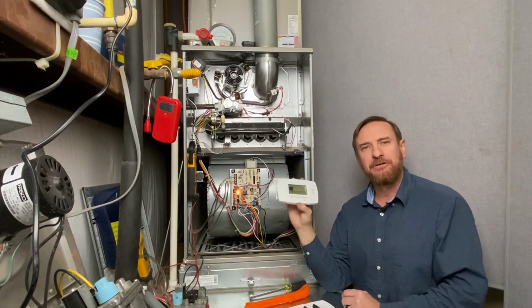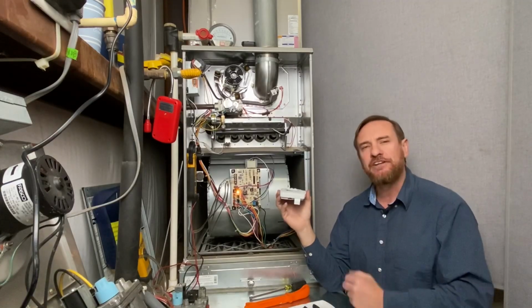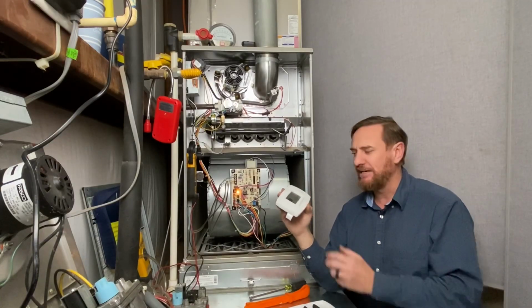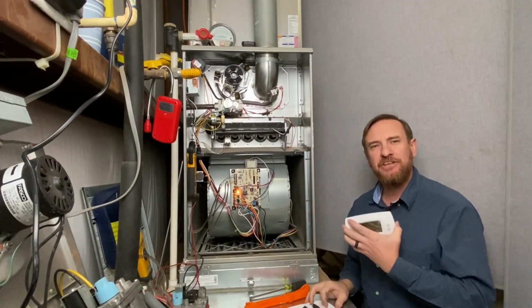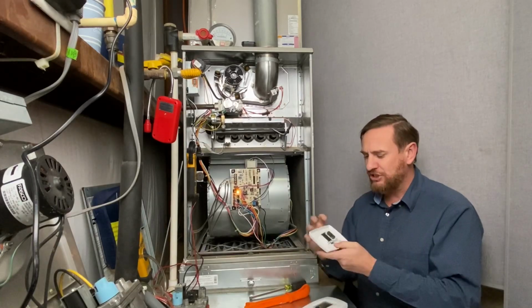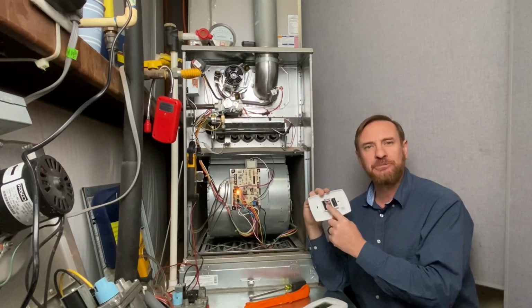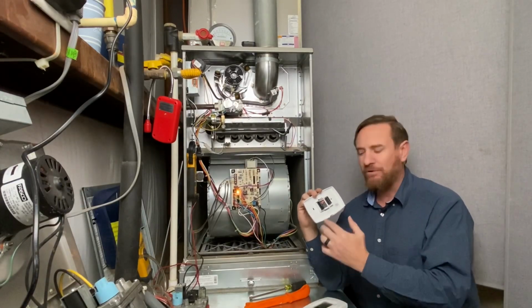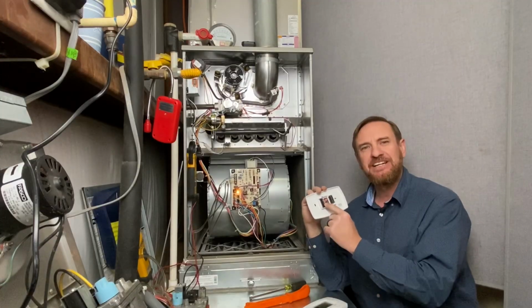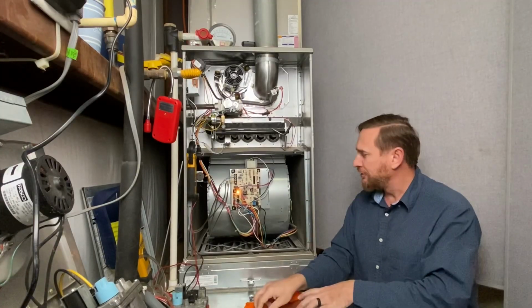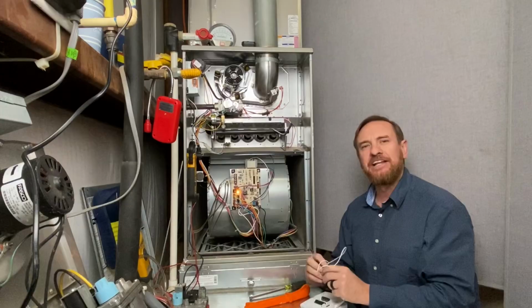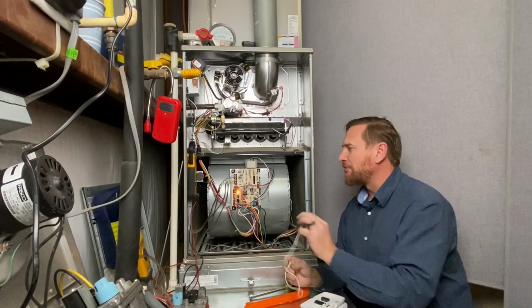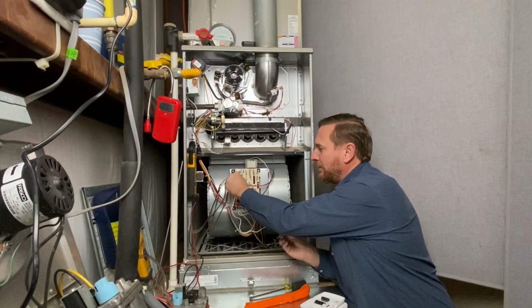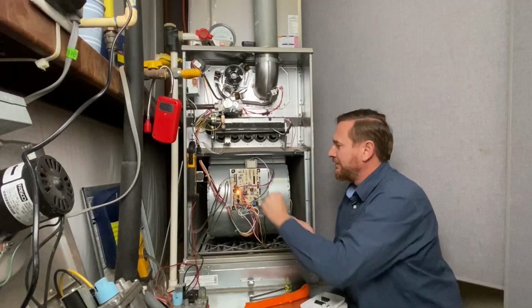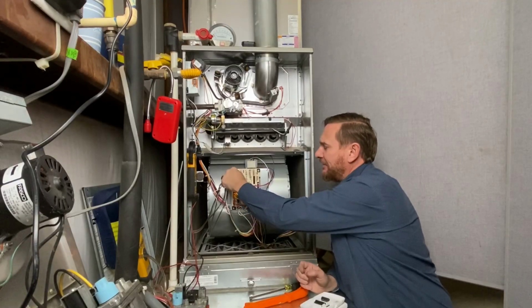One step is the thermostat calling for heat. The phrase calling for heat is a vocabulary term that we use in the trade. The thermostat's nothing more than a switch. That switch connects the R and the W terminal. You can use any color wire you want, but the terminals it's connecting are R and W. On the control board, we also have an R and W terminal. So on the control board, we're just going to jumper R to W to do exactly what the thermostat does.